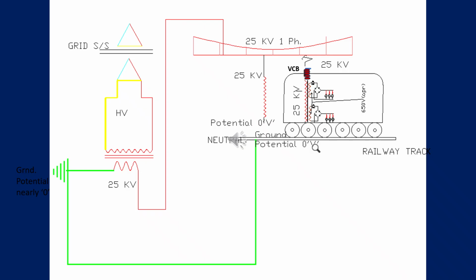to the transformer, but through an insulated path, so that it should not touch the body of the locomotive. The metallic body of the locomotive is at ground potential. If you directly touch the body, it will be a short circuit, phase to ground. So we are using an insulated path to come to the transformer inside the locomotive, and we are receiving this 25 kV from the roof of the locomotive, and the other end is connected with the body through some arrangement, through some resistance, through some switch, so many things. I'll discuss it later.